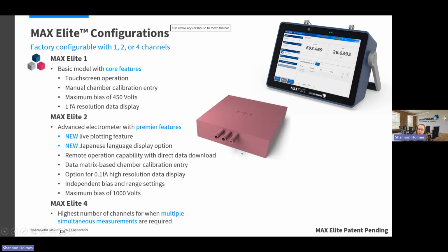So a couple places where people are using those additional channels, we have a chamber intercomparison jig where you can get rid of the need for radioisotope-based check sources and check your chamber stability just using an accelerator instead. So it's an intercomparison for 3 chambers. That way, if one chamber has been damaged and is no longer providing stable signal, there are 2 other channels that are chambers that you can use to compare with it. Again, just to enable you to do that stability measurement without necessarily having to have a radioactive check source.